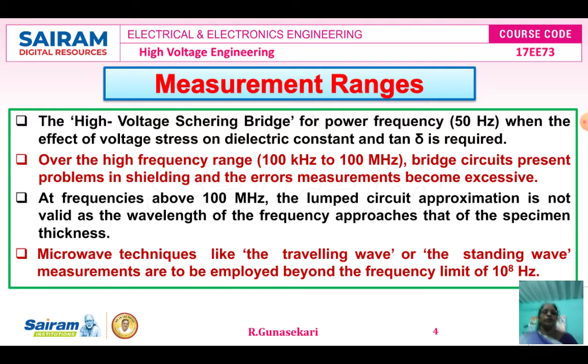The variation and sudden changes in the tan delta value, obtained from the measurement of tan delta and the complex permittivity, help in assessing the quality of the dielectric and the insulation system. The applied voltage indicates the inception of partial discharge, denoted by PD, during the variation and sudden changes in the loss factor tan delta value. This partial discharge is used to determine the inception level of the internal discharges and internal losses due to partial discharge in the high voltage measuring equipment.